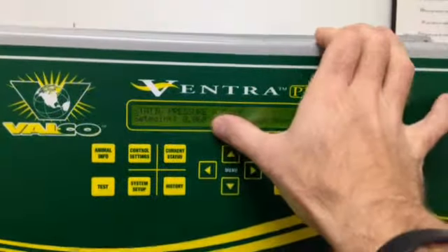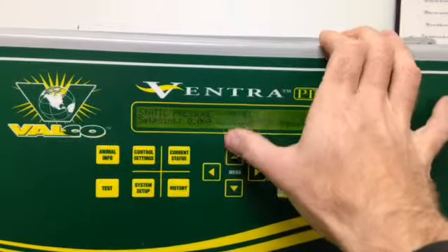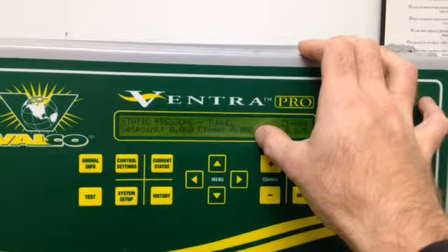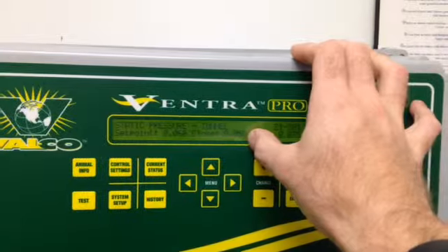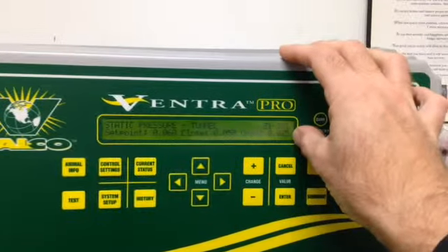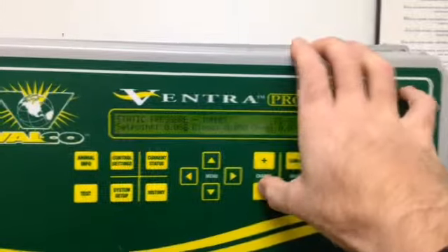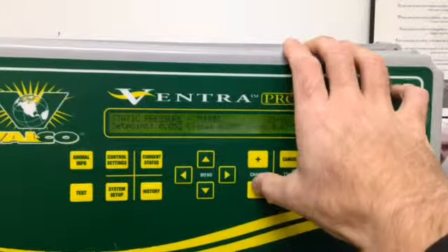pressure. Currently we have a set point of 0.06 inches of water column, closing the curtain if it ever gets below 0.05 inches of water column, and opening the curtain if it ever gets above 0.075 inches of water column. 0.06 is a good number to start from. Anywhere from 0.05 to 0.08 would be an acceptable number.